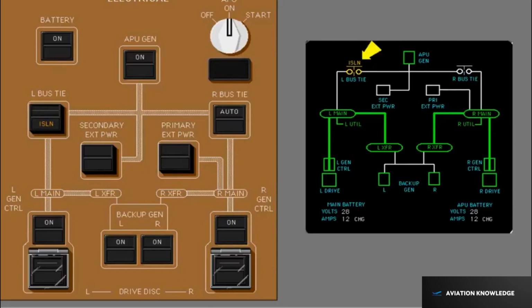Faults associated with the isolation lights are covered in another lesson. However, notice that even though the right bus tiebreaker is open, the right bus tie isolation light remains extinguished. The isolation lights always remain extinguished when the bus tie switches are in auto and the bus tie breakers are performing their normal automatic operation.